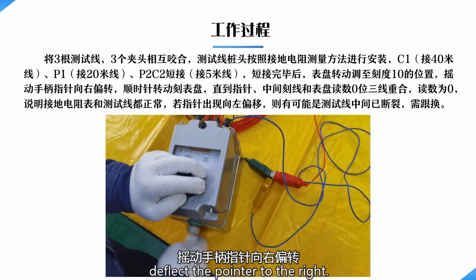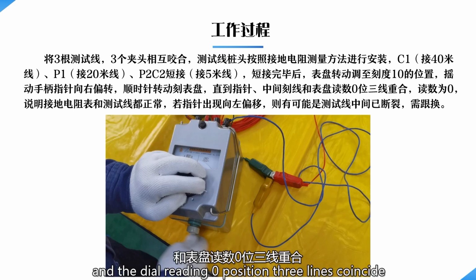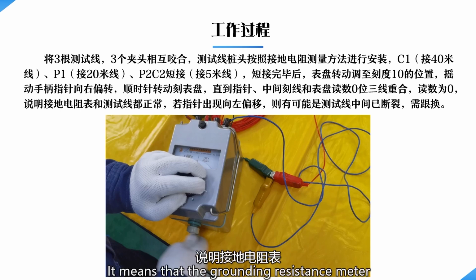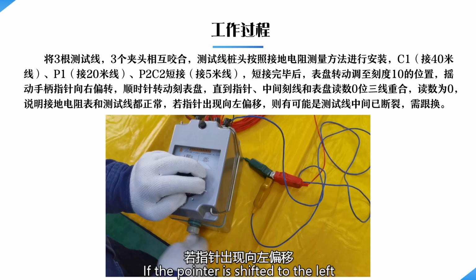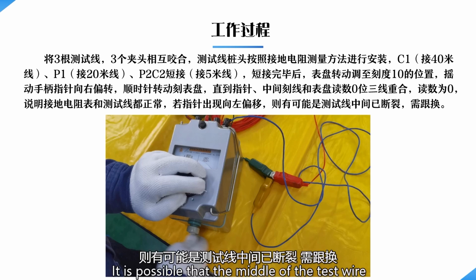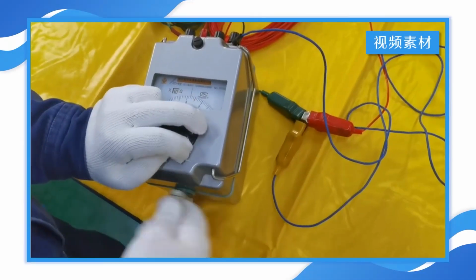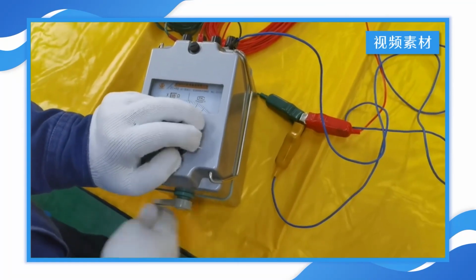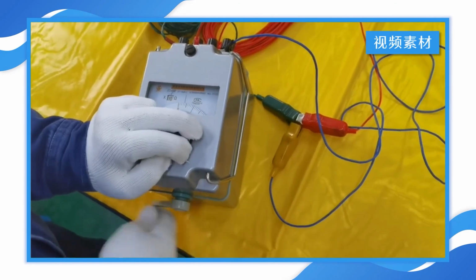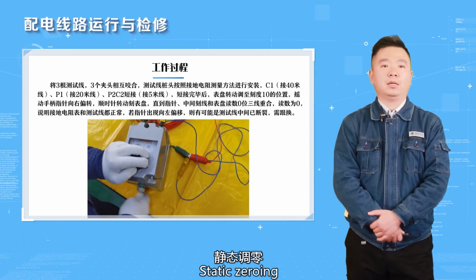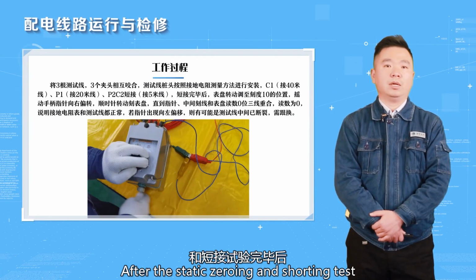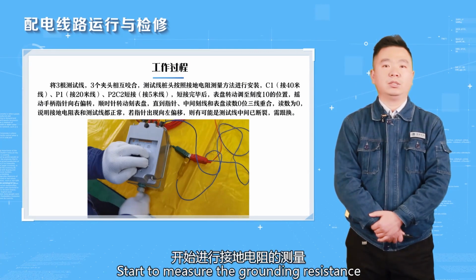Shake the handle to deflect the pointer to the right. Turn the dial clockwise until the pointer center line and the dial reading 0 position coincide. The reading is 0. It means that the grounding resistance meter and the test line are normal. If the pointer is shifted to the left, it is possible that the middle of the test wire has been broken and needs to be replaced. After the static zeroing and shorting test, start to measure the grounding resistance.